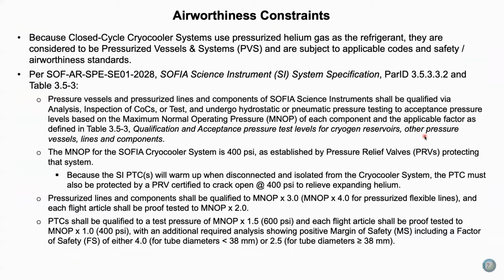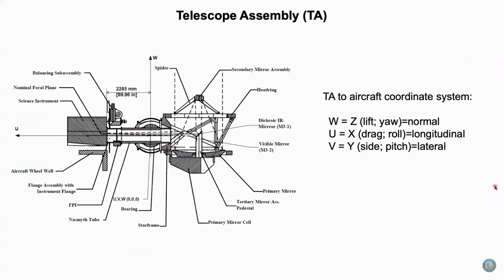And then finally, airworthiness constraints. This mainly, for our purposes, refers to pressurized systems. Like a pulse tube is a pressurized system, pressurized vessel, flex lines as well. And also sorption refrigerators - those are pressurized with helium when they're at room temperature. So those are potential safety problems. They have to be certified airworthy.